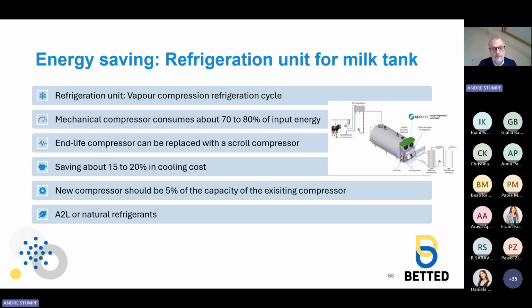Okay, now we will speak about the refrigeration unit for the milk tank. The refrigeration system operates using a vapor compression cycle of refrigerant gas. The mechanical compressor is a component in the refrigeration system that compresses the refrigerant vapor from the evaporator pressure to the condenser pressure, consuming about 70 to 80% of the input electricity to the system. Replacing an end-of-life compressor with a scroll compressor, for example, can save 15 to 20% in cooling cost because of the lower electrical demand.